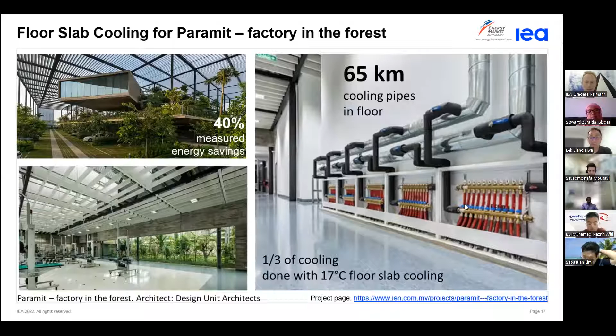So for this building, we laid about 65 kilometers of this cooling system, and once it's embedded in the concrete, it can last for 100 years. So unless you drill through the concrete floor and puncture the pipe, there should be no problem maintenance-wise. And even if you do drill into the floor, you can hack down and repair it if need be. Or you can switch off that loop on these manifold pipes that is affected.